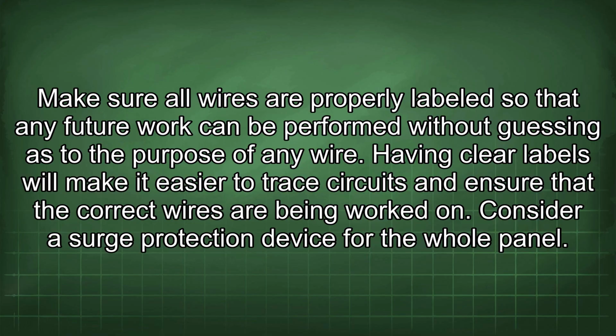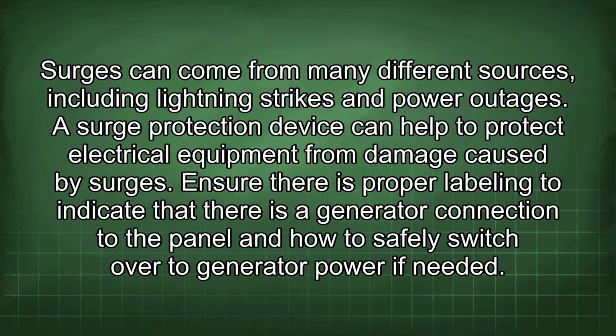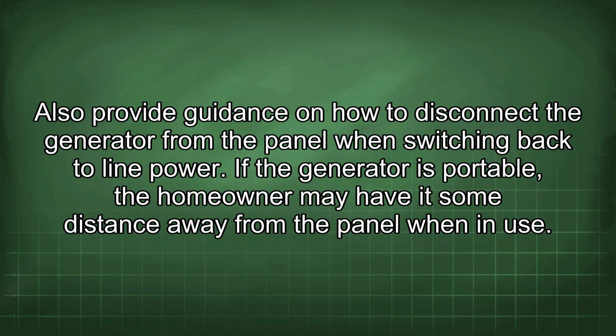Consider a surge protection device for the whole panel. Surges can come from many different sources, including lightning strikes and power outages. A surge protection device can help to protect electrical equipment from damage caused by surges. Ensure there is proper labeling to indicate that there is a generator connection to the panel and how to safely switch over to generator power if needed. Also provide guidance on how to disconnect the generator from the panel when switching back to line power.